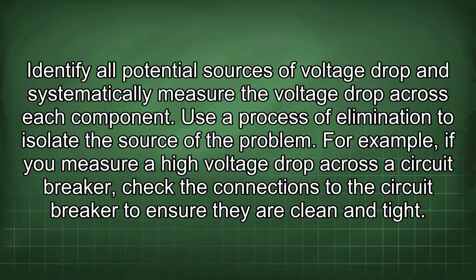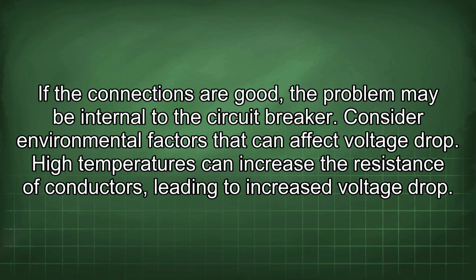For example, if you measure a high voltage drop across a circuit breaker, check the connections to the circuit breaker to ensure they are clean and tight. If the connections are good, the problem may be internal to the circuit breaker.